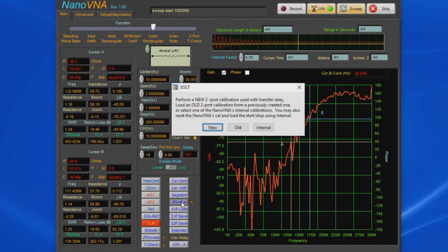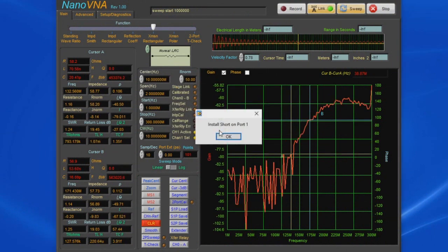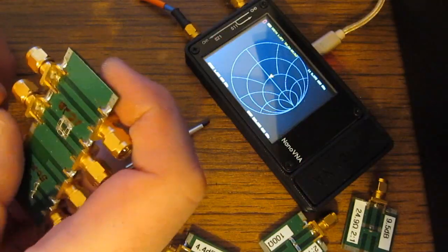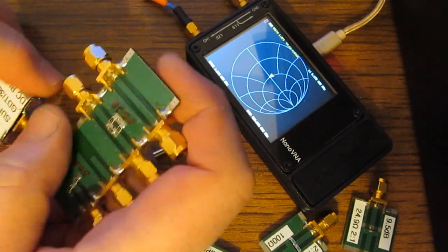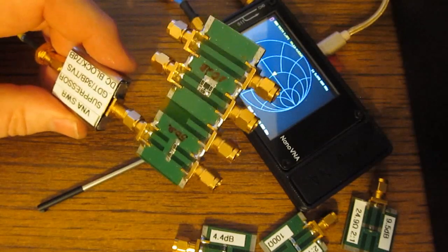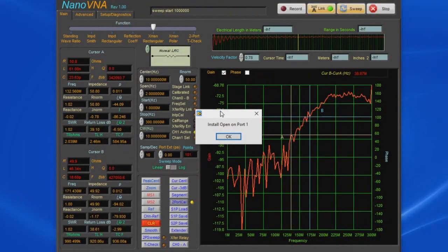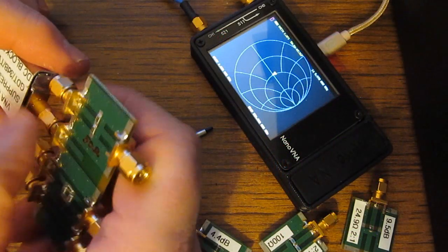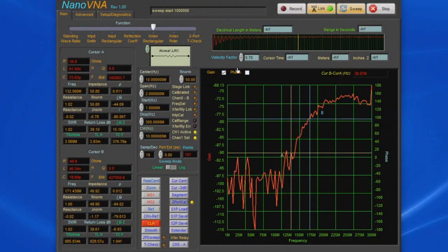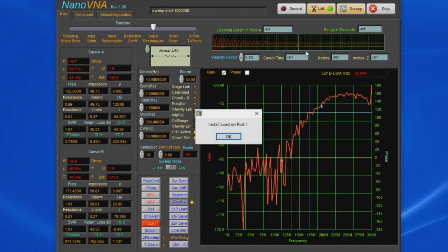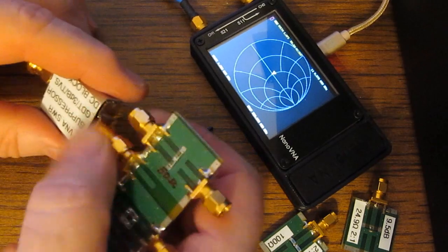So again, to do that, we just select 2-port cal, we select new, and we apply the short to port 1. In this case, it's on the back side of our little suppressor. And we install our open. And we install our load.